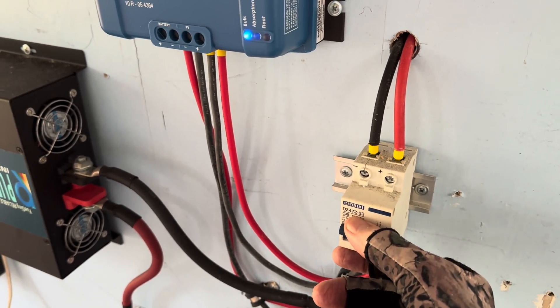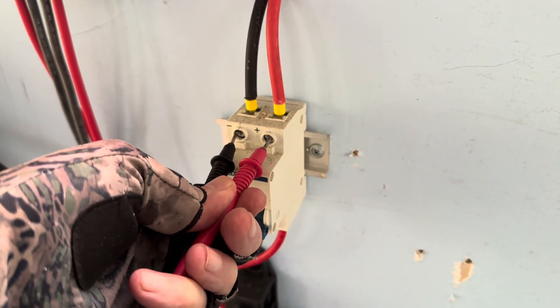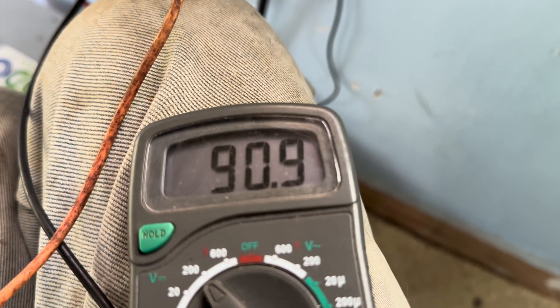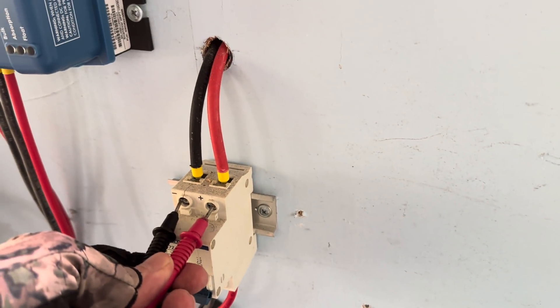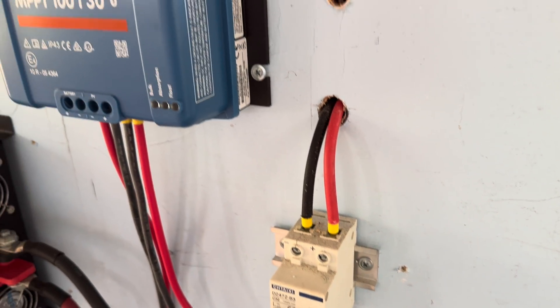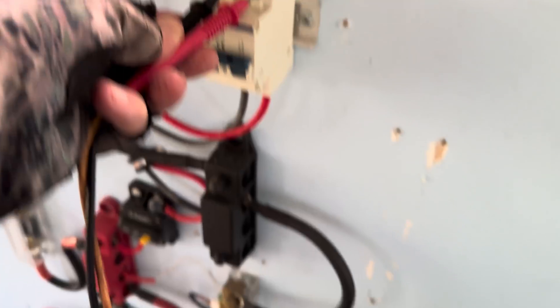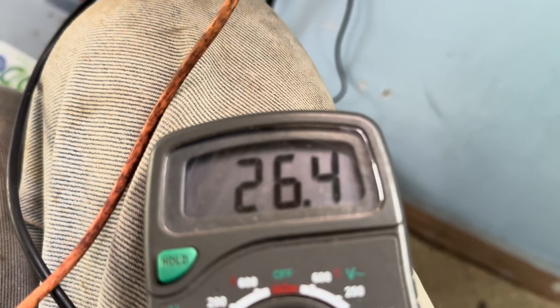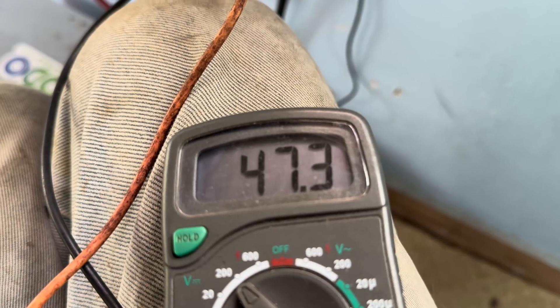This is per Robert out there in New York — it was a good suggestion. That breaker is turned off, and we're just measuring how that array looks now in voltage. And that's about more like I would like to see — 90, 89 volts. That jives much better than 45. We'll flip it back on and give it a moment to reconnect. It's all reset. Right back to what the app has been showing all along — mid-40 volts.